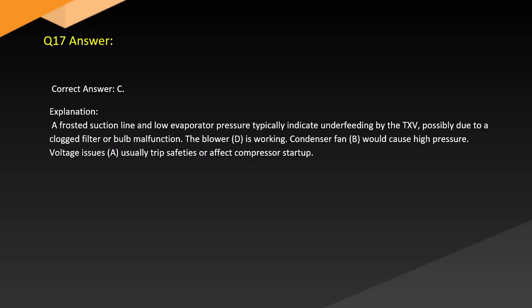Answer. Correct answer: C. Explanation. A frosted suction line and low evaporator pressure typically indicate underfeeding by the TXV, possibly due to a clogged filter or bulb malfunction. The blower D is working. Condenser fan B would cause high pressure. Voltage issues A usually trip safeties or affect compressor startup.